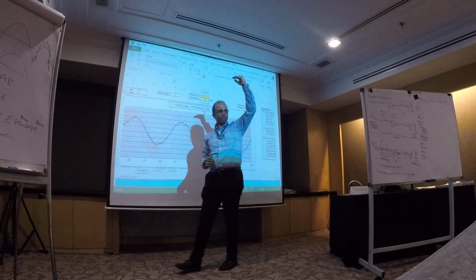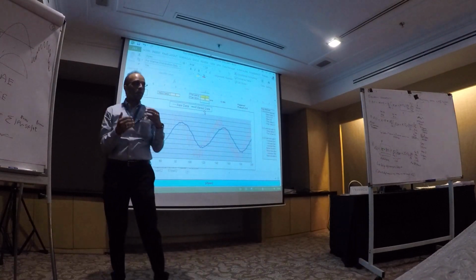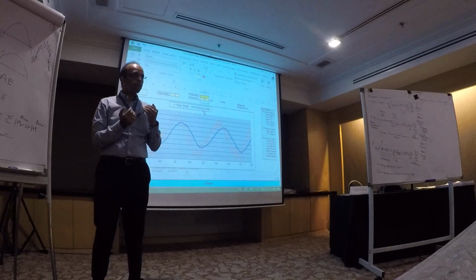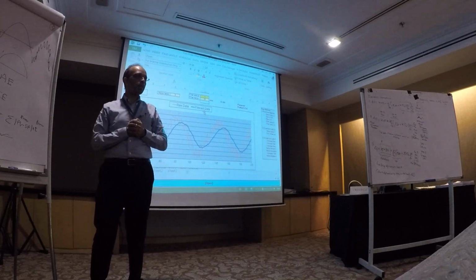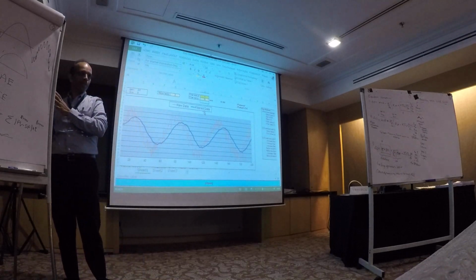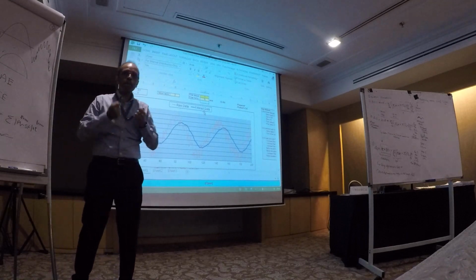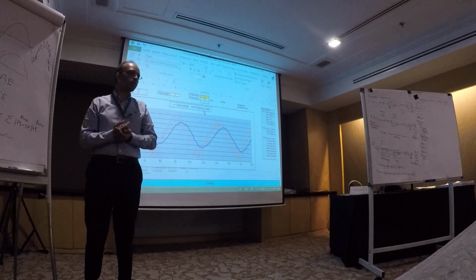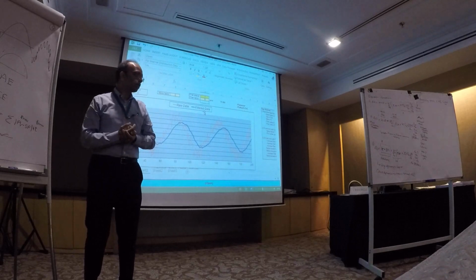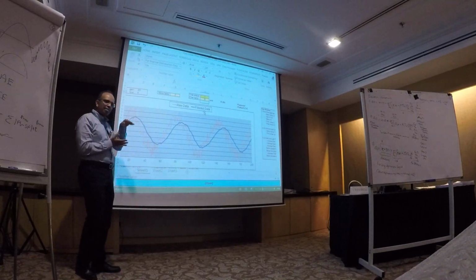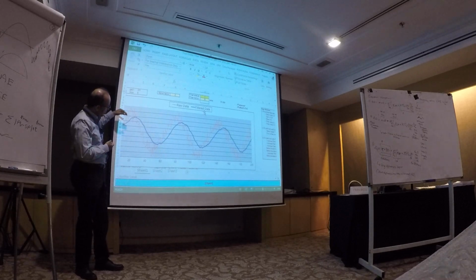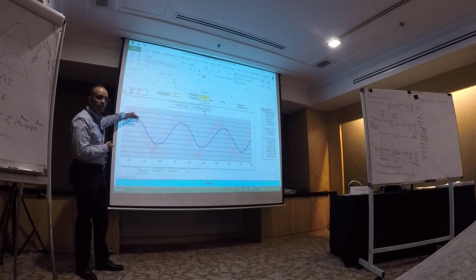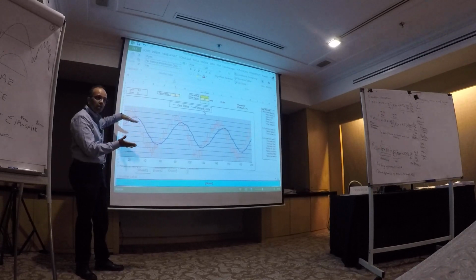So the process reaches a peak, but if you apply a filter, the panel operator won't see that peak. He will see it later. So there's a danger in applying too much filter because you introduce a lag to the process. Okay? And there's something else that happens if you notice. You reach a peak here, but with the filtered output, it's starting to decrease.